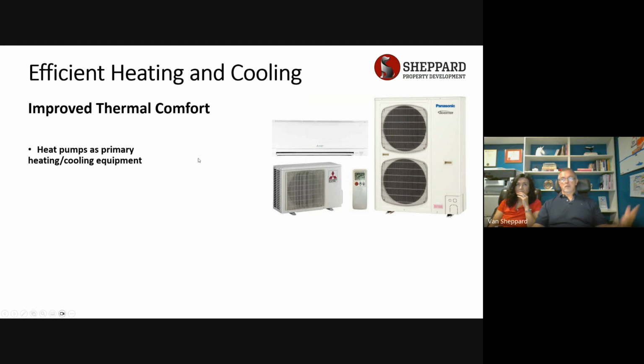So let's say you need 50,000 BTUs in your building, that's actually a pretty big building. Well, in a net zero building, let's say you need 25,000 BTUs. To get 25,000 BTUs from a gas furnace, you need 25,000 BTUs of input. From a heat pump that's operating at about a coefficient of performance of 3, you need about 8,000 BTUs of energy, and we'll get you that 25,000 BTUs out. So heat pumps are a pretty powerful means of providing that efficient heating and cooling. Improved building envelopes allow for smaller heating and cooling equipment. So where you might have needed a 60,000 BTU furnace in a conventional home, in a net zero home of the same size, you could probably size a 25 or 20,000 BTU system, and it would run your building just fine.